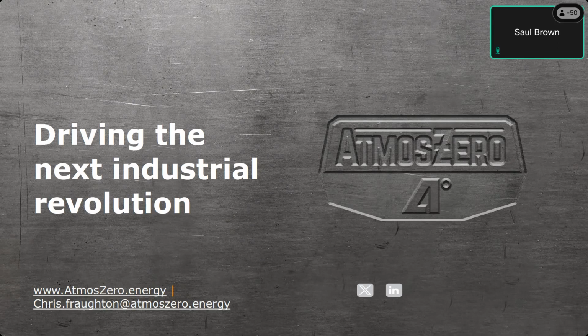What is the outdoor temperature you said requires a shift to resistance? Today, we make the cutoff at -20. We're looking at extending that in the near future. I mentioned the R&D pipeline. One of the things they're working on is a partial hot gas bypass, where you can still source a piece of the energy from colder temperatures than that. That's just going to be a software update that we'll push to all the units probably in 6 months. But as of today, call it -20F. Or sorry, -20C, which is -4F.